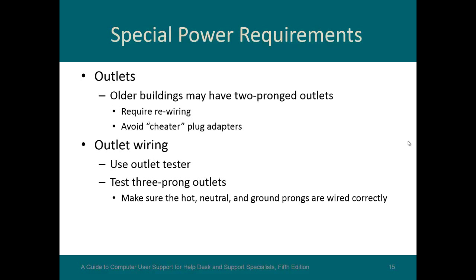Check the wiring in your outlets, especially in older buildings—any building over 20 years old. Years ago, like in the 50s, we had knob and tube wiring, and a lot of buildings still have weird leftover setups that people have rigged to make work. The last thing you want to do is use cheater plug adapters to put a 3-prong into a 2-prong outlet. That might be okay for hedge trimmers you use four times a year, but not for a $40,000 server. If you don't have the right plug, most places have an electrical tester so you can test the hot, neutral, and ground prongs to make sure they're all working correctly.